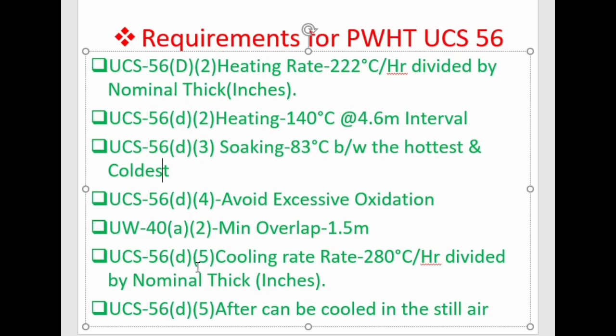The next requirement is UCS-56 D5 — the cooling rate. The cooling rate shall be done in a closed furnace or cooling chamber at a rate not greater than 280°C per hour divided by the maximum metal thickness of the shell or head plate in inches.